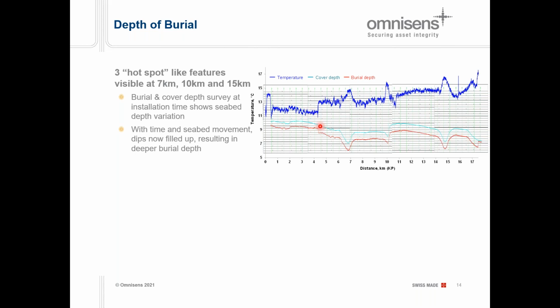It was a bit puzzling to see that when the seabed was a bit deeper, we had an increase in the temperature. But we realized later on, which seems obvious when I say it, that there was a long time between the survey and the first measurement, and actually the seabed had moved and become flat. So instead of a seabed going up and down, we had a flat seabed with the cable going deeper into it. And sure enough, if the cable is deeper in the North Sea, then you get a warmer cable, which explains the kind of signatures we had there.